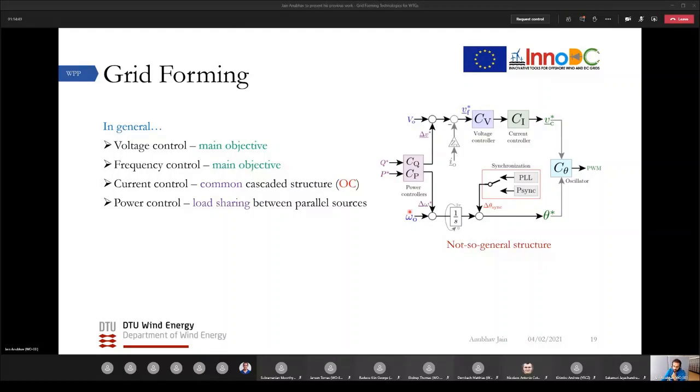And the simplest method for power sharing is, again, what comes from synchronous machines operated in power systems, and what has also been developed in microgrids: droop-based sharing, right? It's very easy to implement. There is no communication required, which is quite important, I think, for these large offshore wind power plants spanning many kilometers, where communication links can be a weak point. While in microgrids, this is not really a worry, I think. That being so, droop-based power controllers are quite easy to implement, very flexible, with high reliability, but they suffer from an inherent trade-off between the load sharing and the voltage or frequency deviation, right?